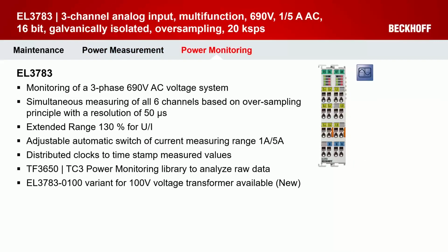Another candidate that is part of the power monitoring classification is the EL3783. It's also designed for 690 volt AC three-phase systems. As explained before, we have a resolution of 50 microseconds based on oversampling principles. Some highlights we have implemented here: first is the extended range of voltage and current of 130%. And in case of a short circuit or a near grid fault, we want to analyze even this very high current, which is maybe 9 times higher than the rated current. We can automatically switch the measuring range from 1 amp to 5 amp within one cycle. So for the 1 amp range and the 5 amp range we have the same resolution, but in case of a fault, we can analyze rated and overcurrent situations in detail.